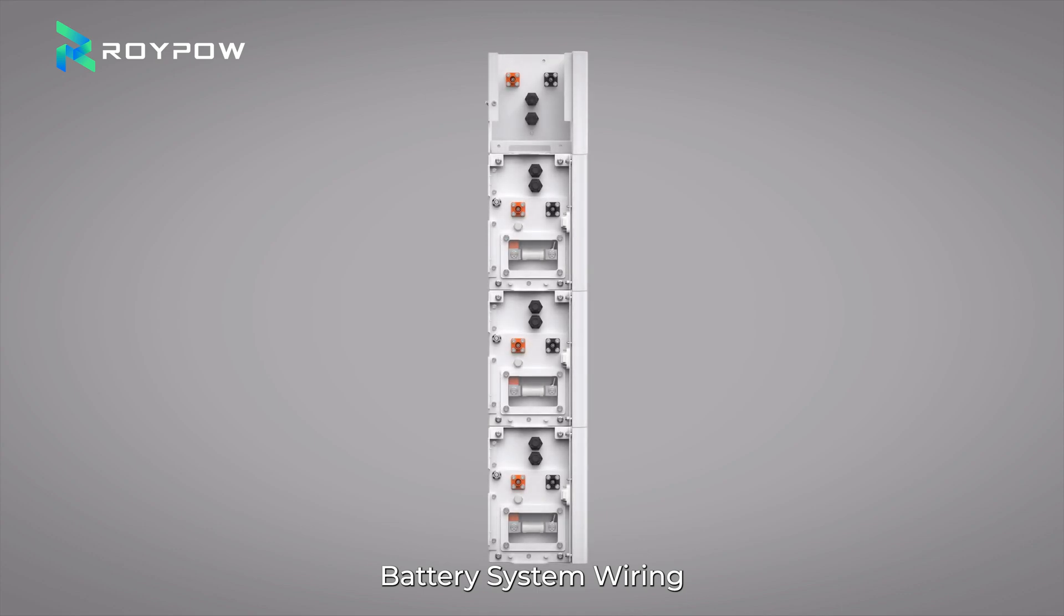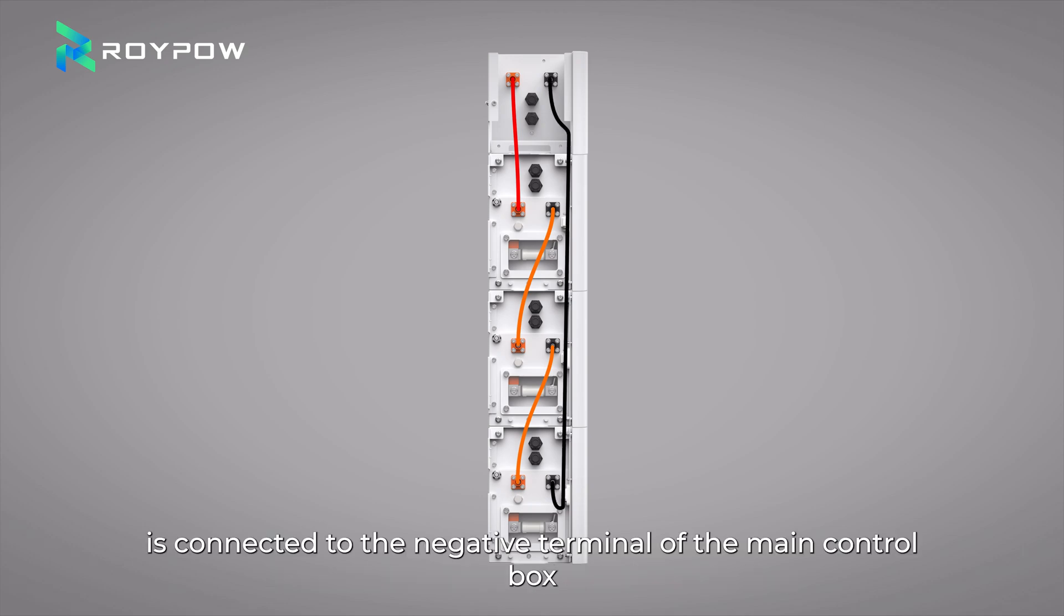Battery system wiring. The batteries are connected in series. The positive terminal of the main control box is connected to the positive terminal of the battery. The negative terminal of the battery is connected to the positive terminal of the next battery, and so on. The negative terminal of the last battery is connected to the negative terminal of the main control box.